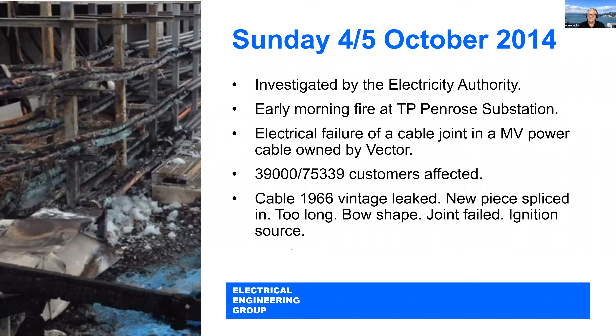It was a 1966 vintage cable that started leaking, and someone spliced in a new piece of cable, but it was slightly too long and had a bowed shape. The joint failed and became an ignition source, causing a fire right inside the substation.